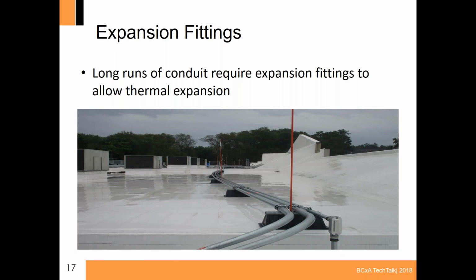Next on the list, and we see this again on the larger commercial scale solar PV systems, is issues with thermal expansion and contraction. So, long runs of conduit across the building where, again, we're up in the Boston area, we're going to have very high temperature variations. Say in the morning it could be snowing, in the afternoon it could be 60, 70, 80 degrees out. I know other parts of the country will be exposed to similar, but even over the course of a year, you have that metal, or sometimes they use PVC conduit, that expands and contracts. And there are tables in the electrical code that allow a certain expansion and contraction, but beyond that, you need a special fitting to account for that.